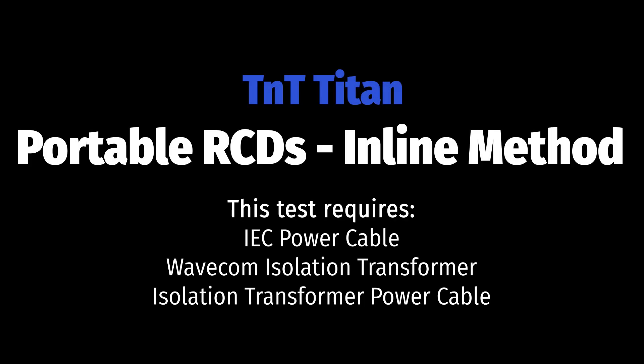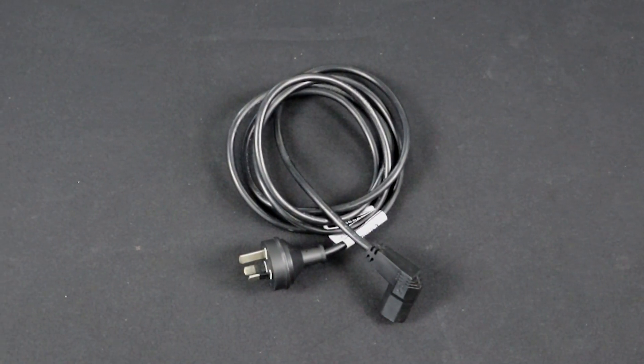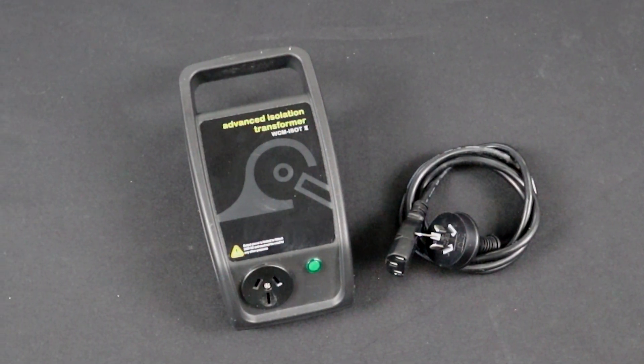If the previous method fails, or you have an older firmware version, you can test portable RCDs using the inline method. For this, you will need the IEC power cable, a Wavecom Isolation Transformer, and the Isolation Transformer power cable.